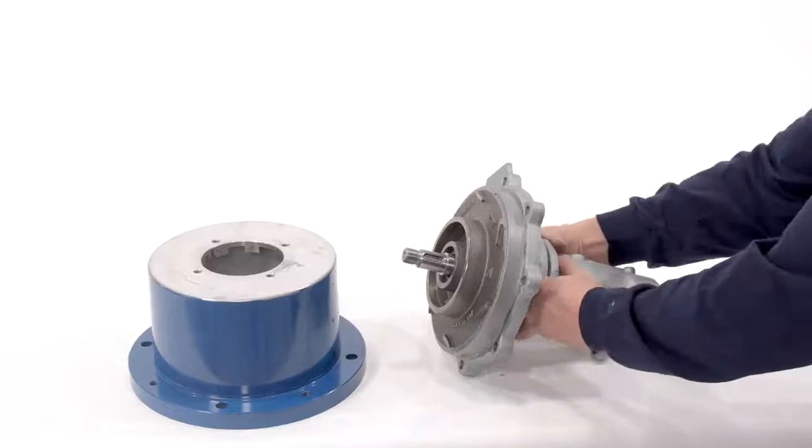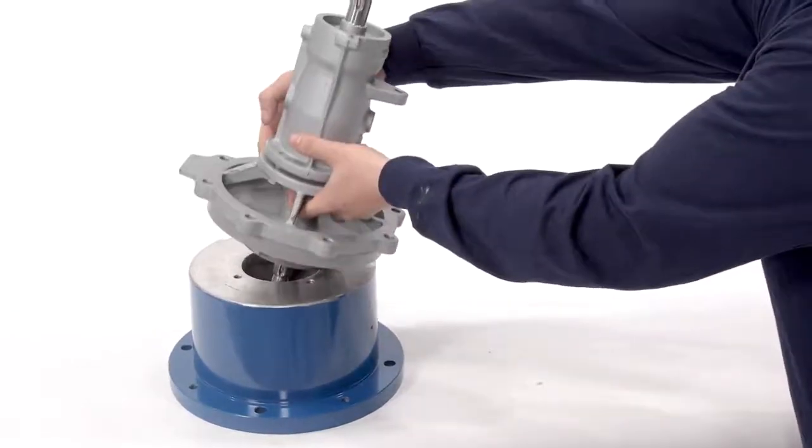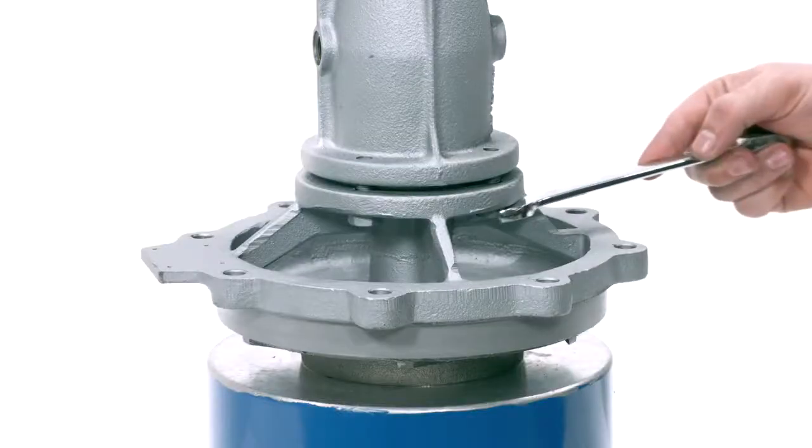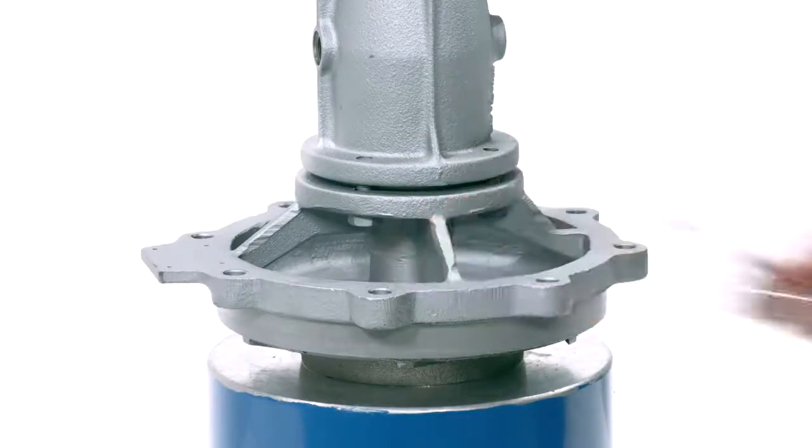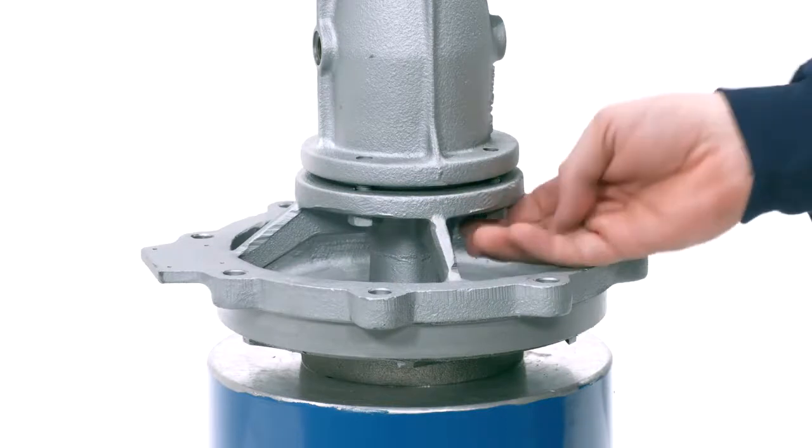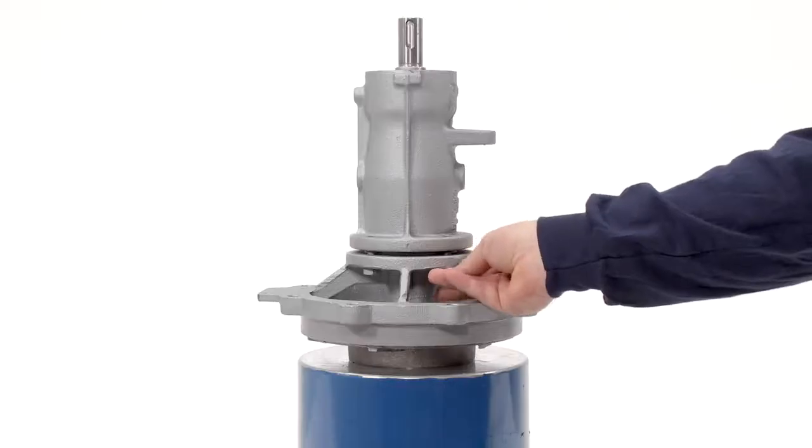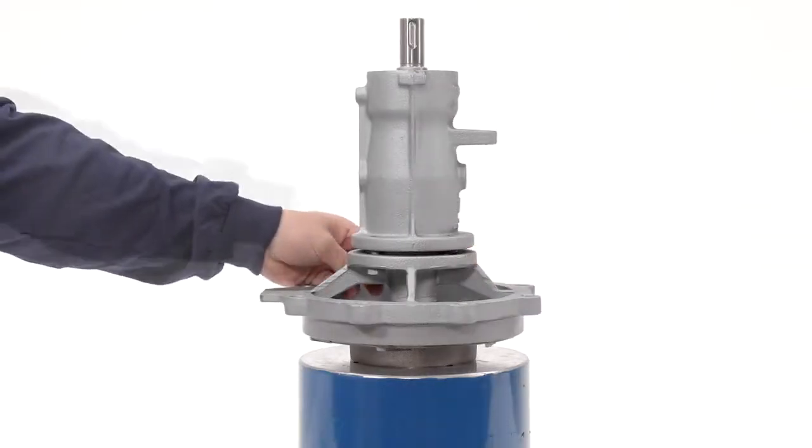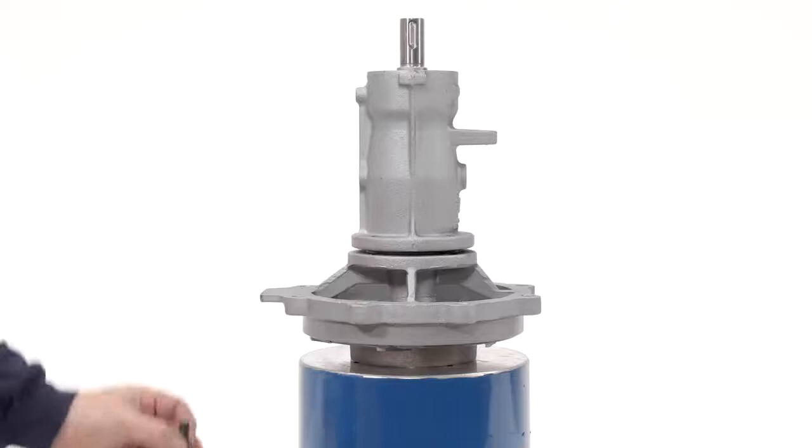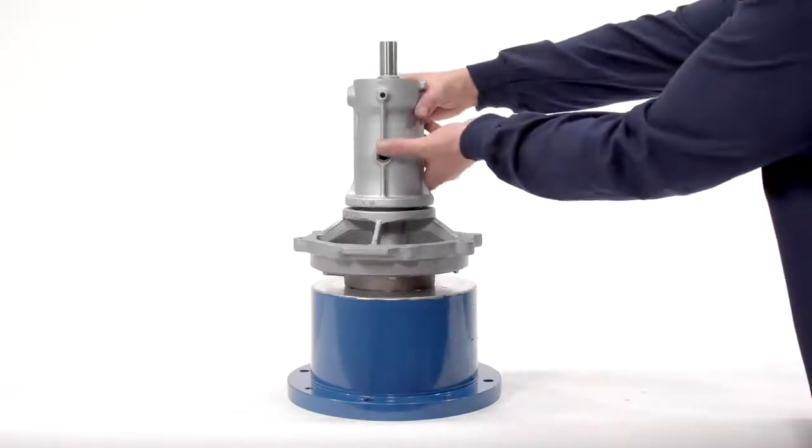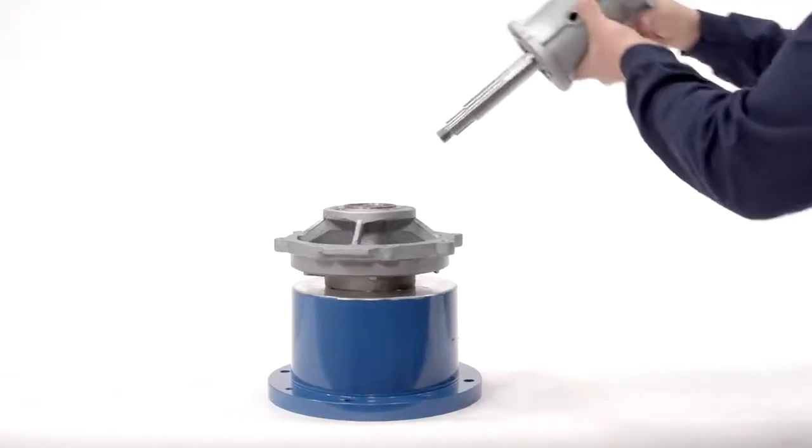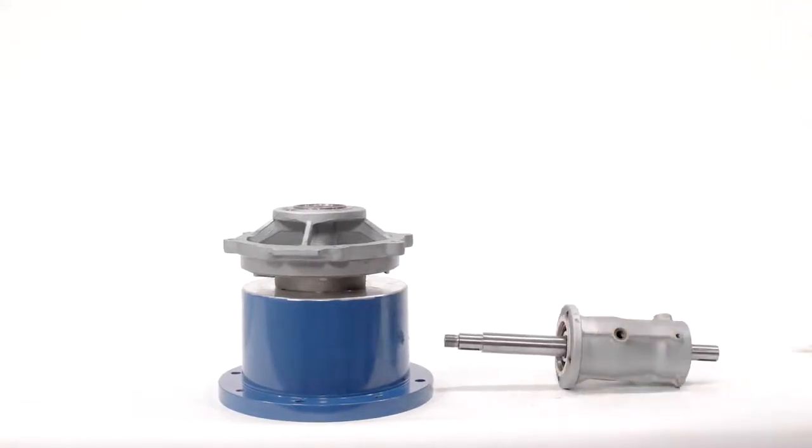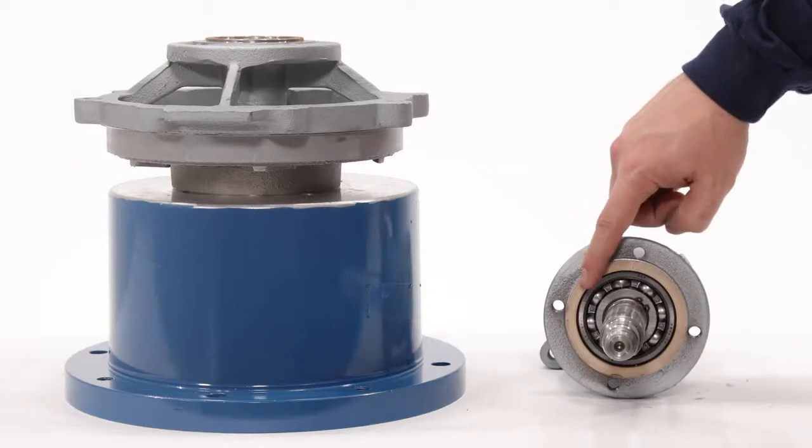Place the bearing housing on a cylindrical stand with the impeller side down. Remove the four casing cover bolts using a 17mm wrench. Lift the bearing housing and shaft up and off the casing cover. Inspect the gasket and replace if required.